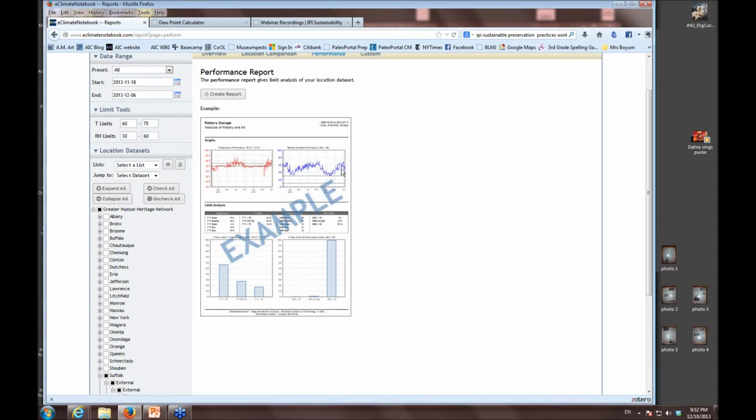Graphically, you can see that they're above this band the whole time, and in this corresponding bar chart, you can see that almost 95% of the time they are above where they need to be on their RH targets. Only for this small point in time have they dropped down.